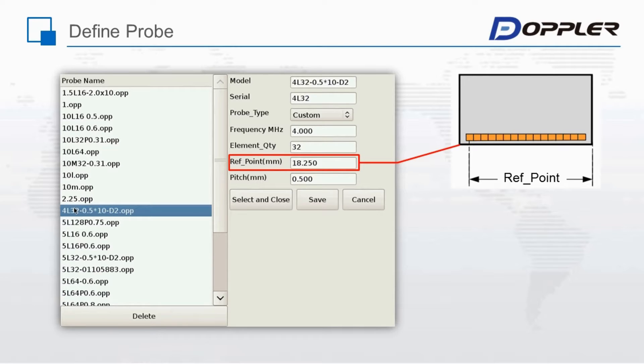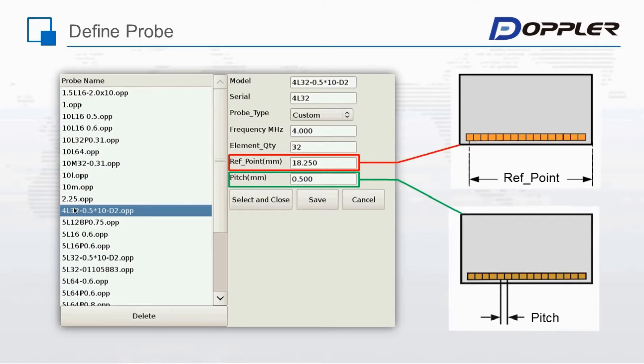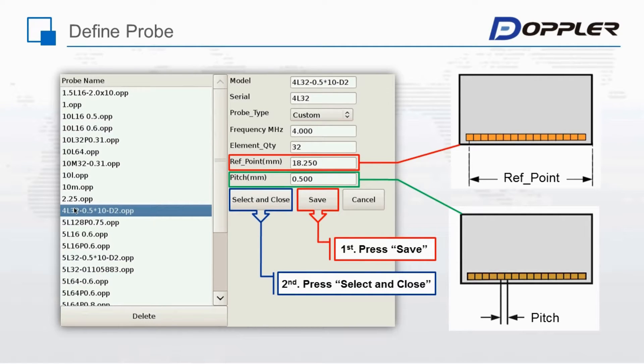How to define non-standard probes: this dialog box will be found on the probe selection menu. Please input parameters accordingly. A specification paper will be attached in Doppler's retail package. Please pay attention to the model name here. The model name could be anything by input, but we strongly suggest users follow the model name in the specification paper to avoid confusion. Save and close.